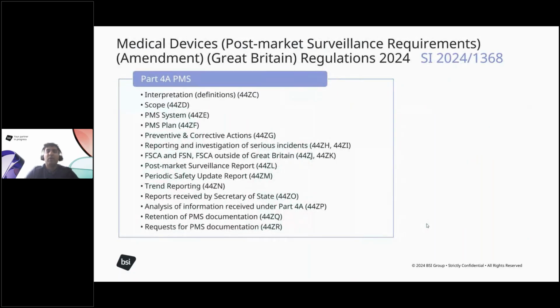So what does this statutory instrument say? The statutory instrument 2024-1368 covers the post-market surveillance requirements under the UK MDR 2002 in Great Britain. So there's a lot of requirements in there, in terms of PMS. It's looking at the PMS system, the PMS plan, preventative corrective actions, reporting and investigation of serious incidents, like I stated, FSCAs, FSNs, FSCAs that are outside of Great Britain, the post-market surveillance reports, the PSURs, trend reporting requirements, reports received by the Secretary of State, and the analysis of information as per Part 4A, but also retention and request of it.